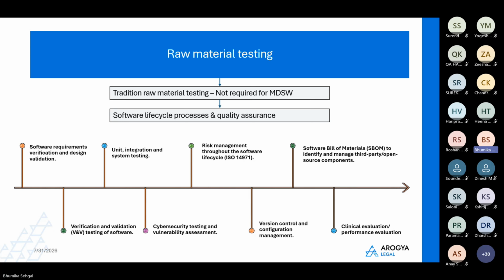So verification and design validation testing is done. Then its integration into a unit and its system testing is done. Then cybersecurity testing and its vulnerability assessment is done for the software, in case there are certain gaps that have to be looked into before its launch into the markets. Then there is risk management. All the risks that are identified throughout the process of testing are documented and looked into before its launch.